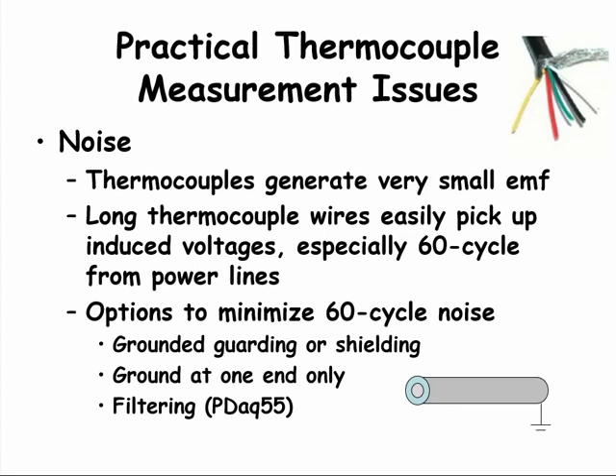Shielding is done by buying thermocouple wire with a shield surrounding the thermocouple wires. The figure in the upper right corner has a silver-colored metal foil that surrounds the 5 signal wires. This figure does not show thermocouple wire. The shield intercepts the induced voltage and drains it away by being grounded. So the foil shields the signal wires from induced voltages. It is important to remember that shielded wires should be grounded at only one end. It is usually recommended, if possible, to ground the wires at the recording device.